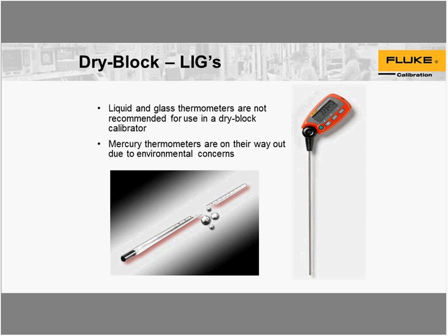One thing to consider that we've come to market with to replace those is our stick thermometer, where we went at the LiG market with an alternate electronic RTD solution. So again, something to be aware of as far as calibrating LiGs in a drywell: you typically don't get super good results, just due to the bulb getting a nice air gap, a kind of insulation effect around it in the well.